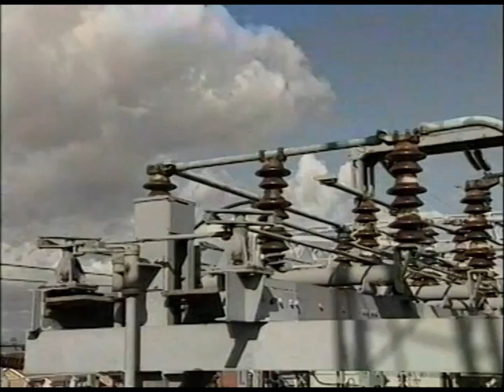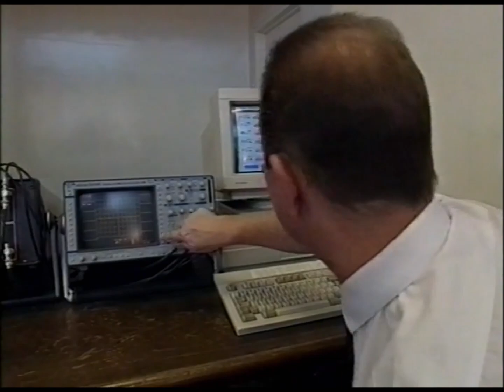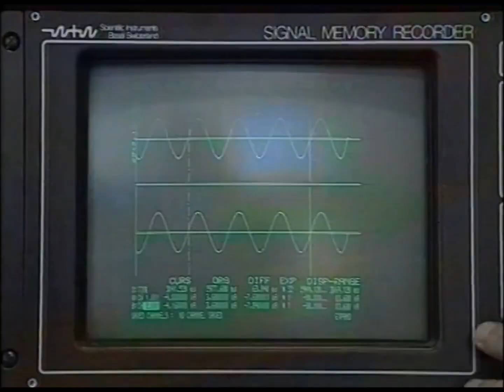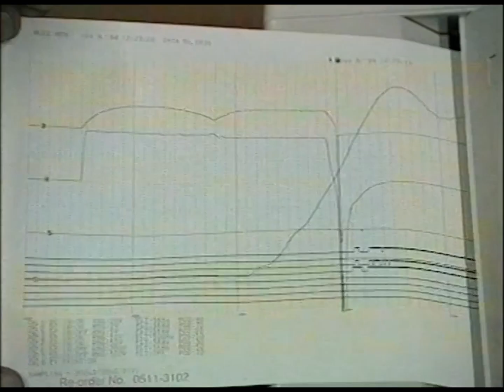This is the heart of the Reyrolle Technology operation, the British short-circuit testing station. It was the first short-circuit test station in the world and is still one of the largest and most versatile. More importantly, it is uniquely independent, operating a completely confidential service for clients. BSTS is fully accredited by both NAMAS and ASTA certification services. That means that independence, confidentiality, test procedures, accuracy of measurements, acceptance criteria, and reporting are accredited and verified by internationally accepted bodies. In other words, documentation from tests imposed on equipment here is fully recognized throughout the world.